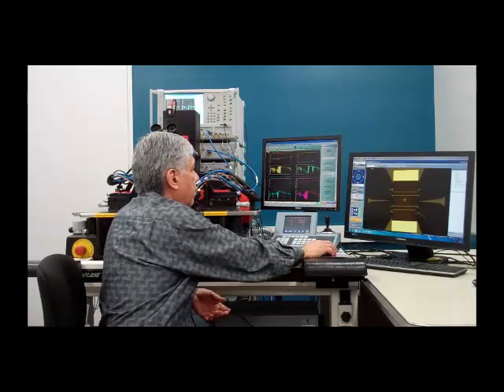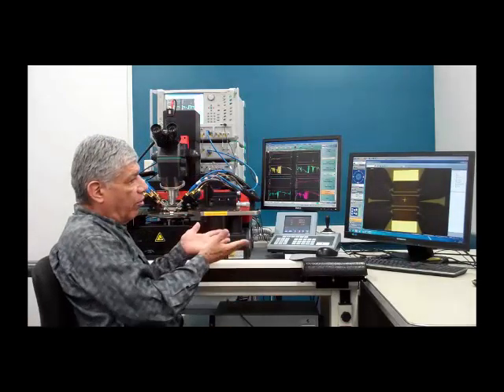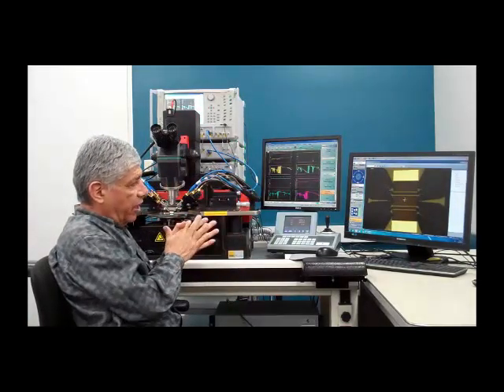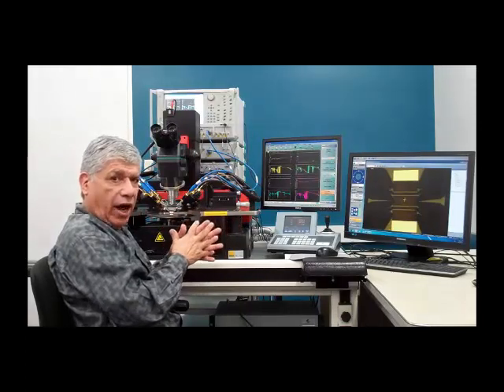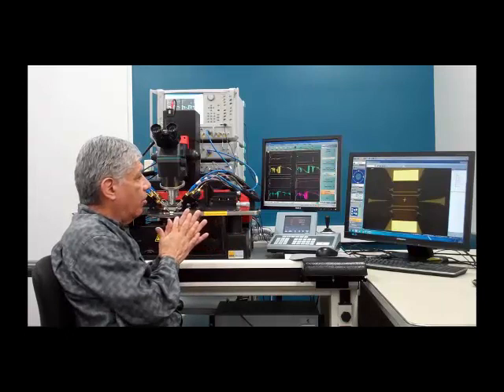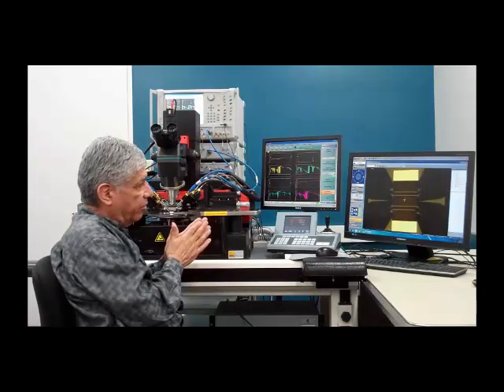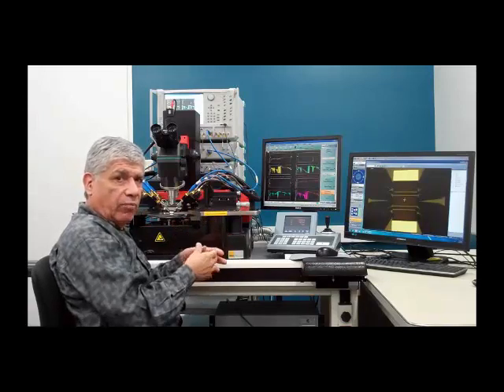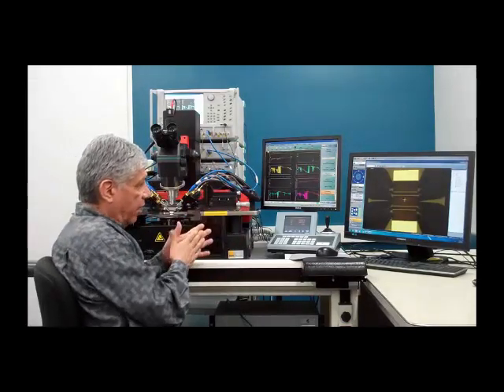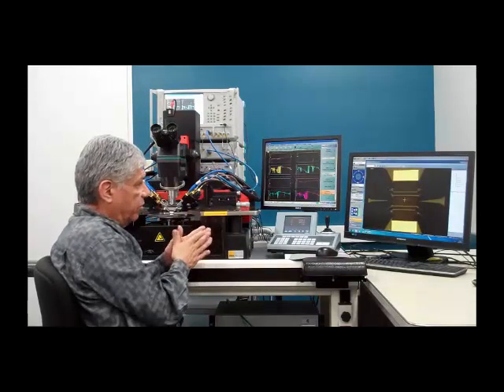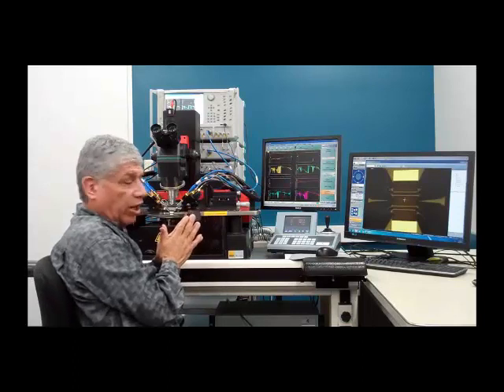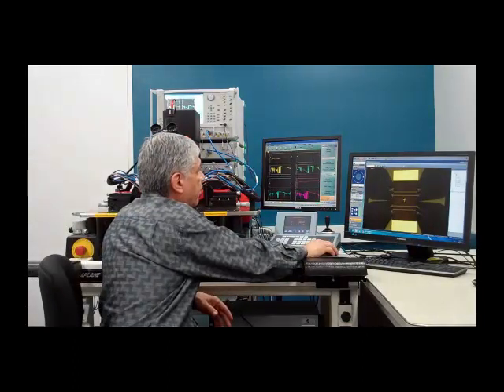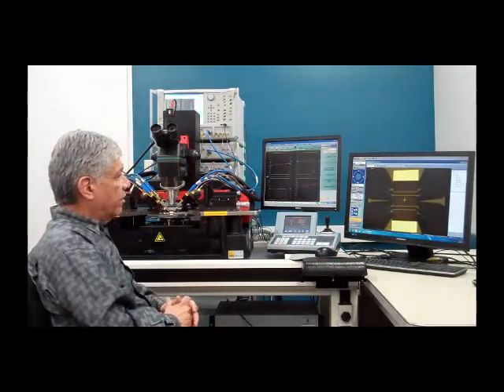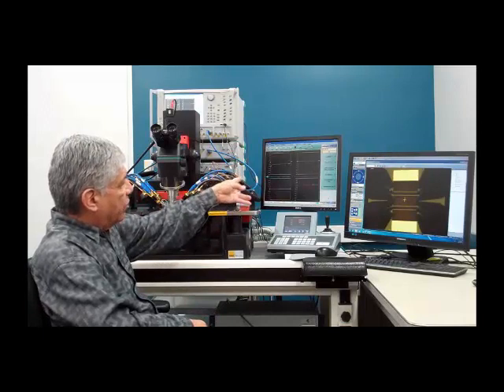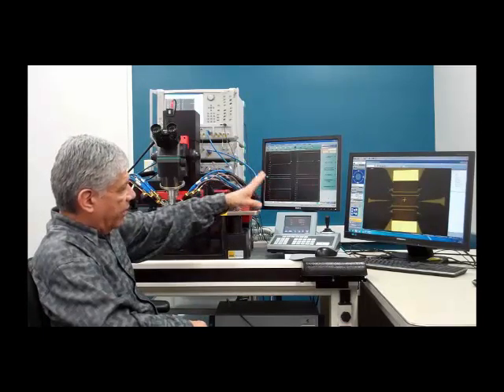So there is the option of doing an isolation, but we found at normal operating levels and typical types of structures, isolation isn't usually needed. So it's optional in case you do have certain situations where your DUT substrate might have some isolation issues in it, and if you're able to duplicate that, then you may be able to use that capability in your calibration structure. Okay, so now we just simply click on Done, and that will give us the ability then to evaluate our calibration, take a look at the characteristics of the through line.